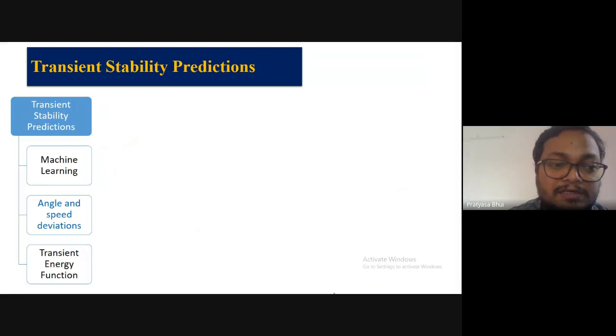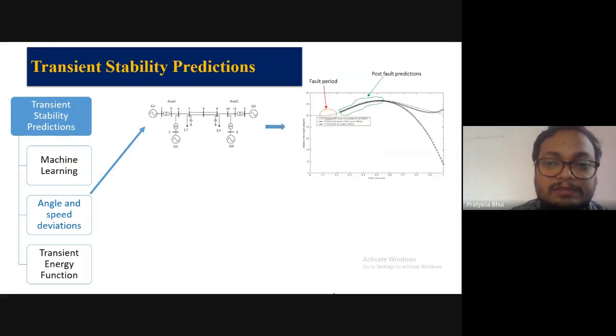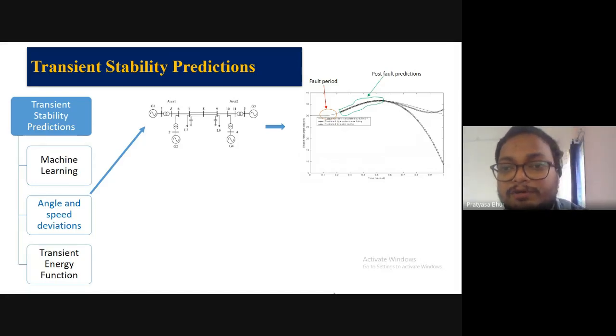So next comes angle and speed deviations. Whenever there is a fault, just after fault clearing, this red circle you can see is the fault-on period. After the fault period, you will have some data here after fault clearing. Use the data to predict the post-fault stability. So you mark a threshold, say if it crosses 180 degrees, it becomes unstable. So use a second-order polynomial to predict whether it will become stable or unstable. So you predict the generator speed or angle, and based on that you take some decisions.